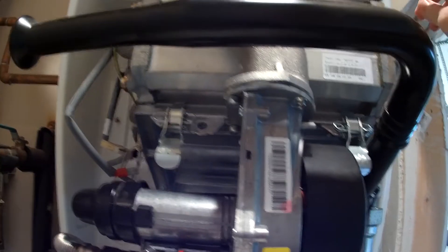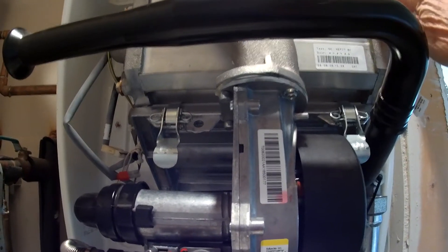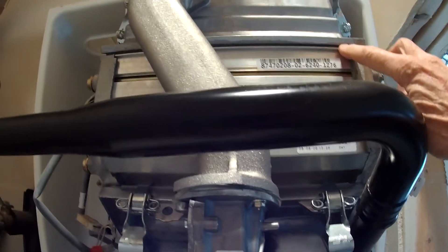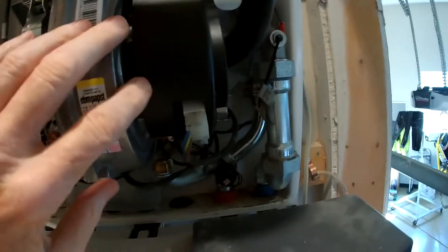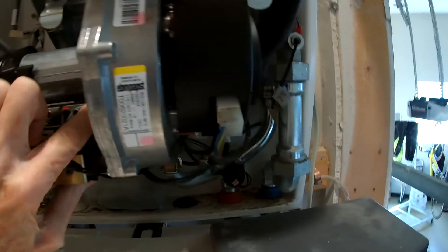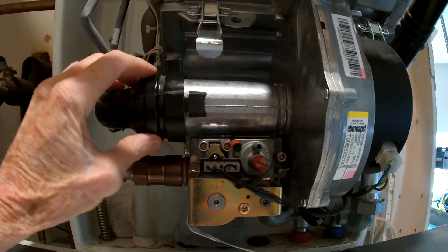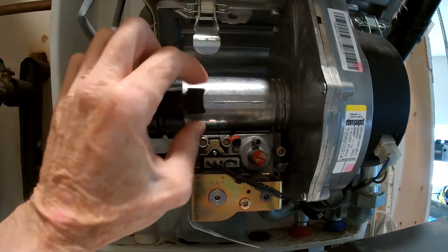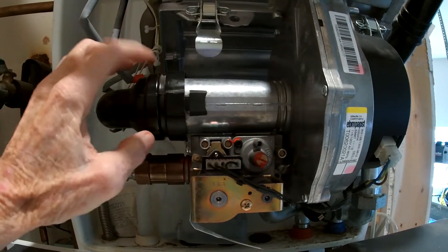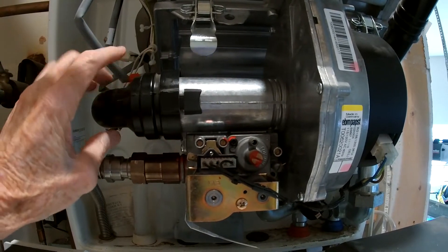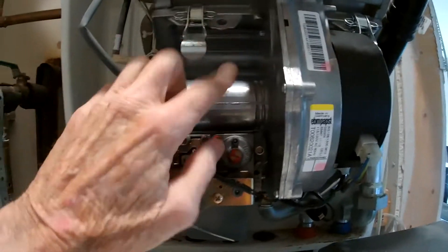Leave this on to start with. When you lift the whole unit off, be very careful that you lift it straight up and real gently, or you'll screw up this gasket up here and it's pretty pricey. So when you get that out, then you'll be able to take this unit, take off the fan here and the gas valve here. And you'll be able to take this off. Be very careful with this because this has some plastic clips in it also that can break. These little caps pop straight off. There's one on either side. Then this will slide out and it'll come out really easy. But you need to do that to switch it to the new fan.